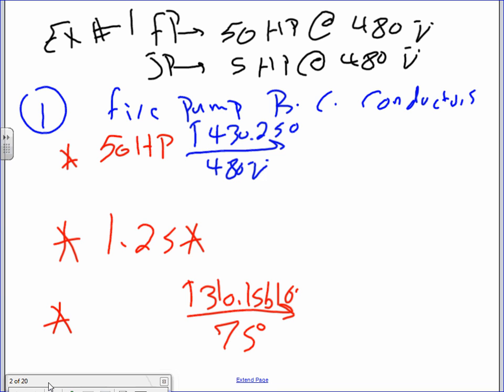Okay, the first thing that you need to do is find the example, like I said, 50 horsepower at 480, jockey pump at 5 horsepower at 480. Fire pump branch circuit. The first thing you need to calculate, and I have that one for you, is the fire pump branch circuit. So you go to 430.250 under 480 voltage, and when you go there, you're going to find it's 65 amps.